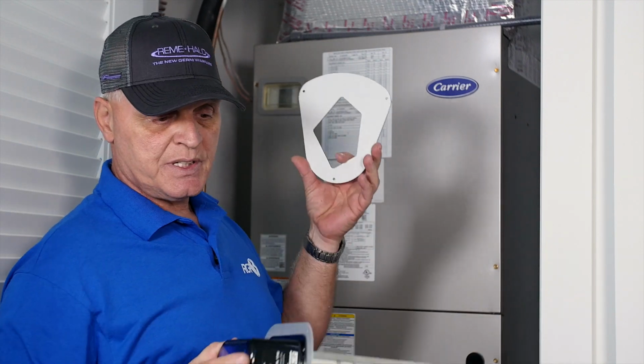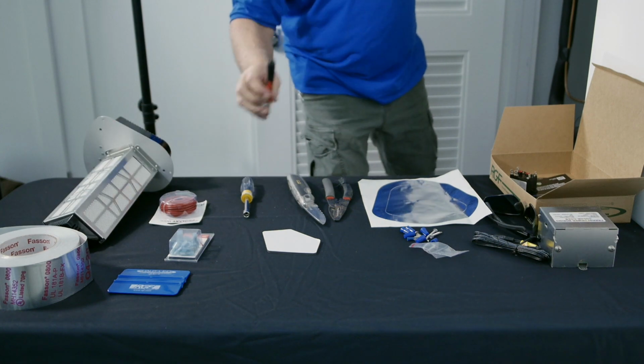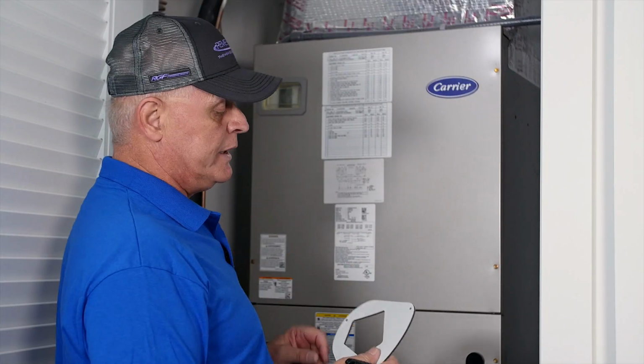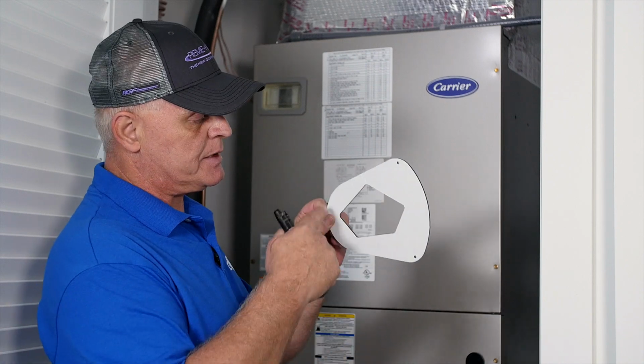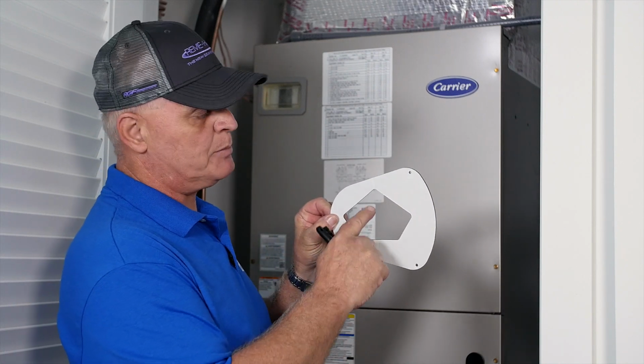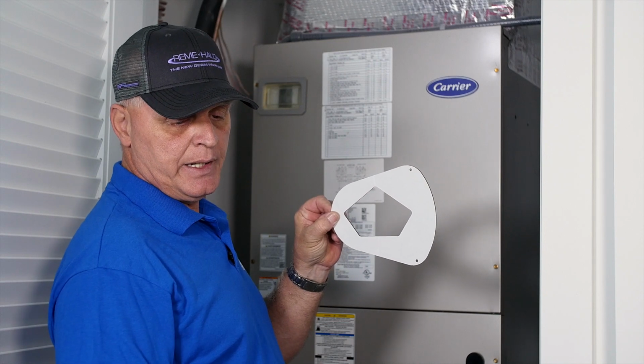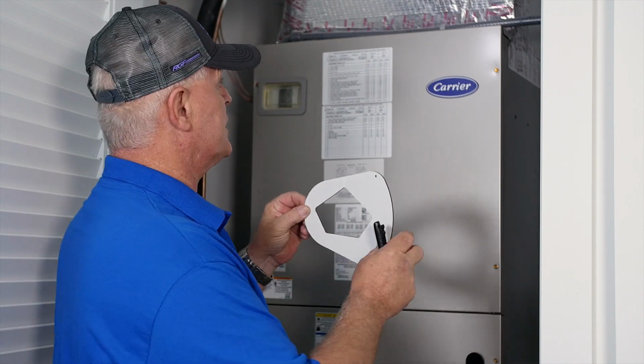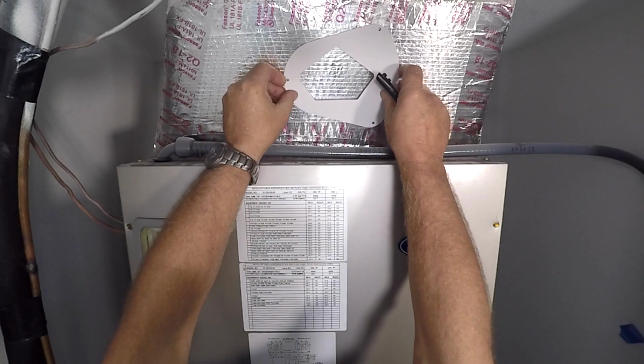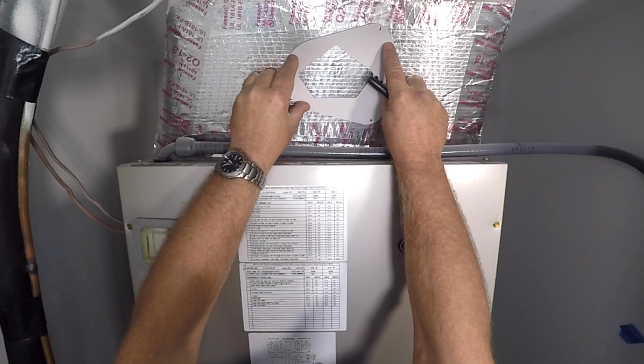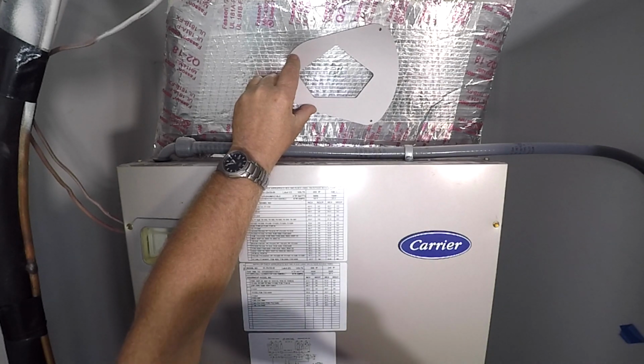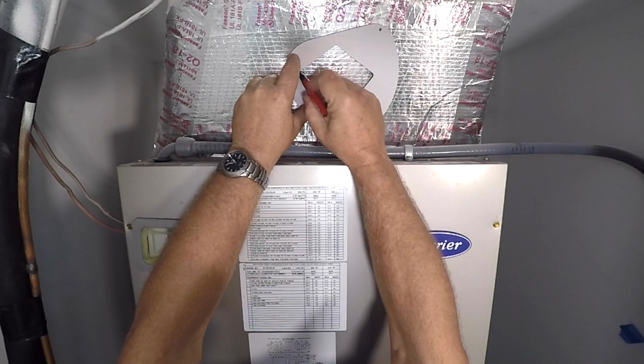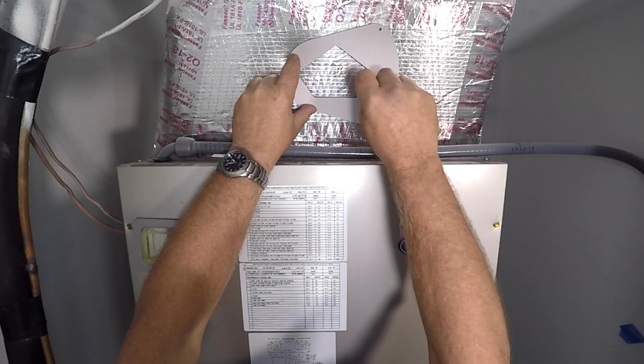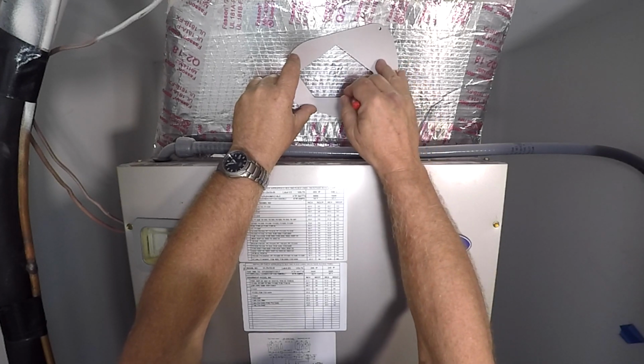I am going to use this gasket as a template to mark where I'm going to cut the hole in the ductwork. Again, remembering that it has to sit in this orientation, the flat on the bottom, the arrow up, and with the airflow pointing up, this is our orientation. So I'm going to set it on the ductwork here, trying to keep it somewhere near the center and square. And then I'm just going to draw a line around the inside of the gasket template, which we are going to cut out with a duct knife.